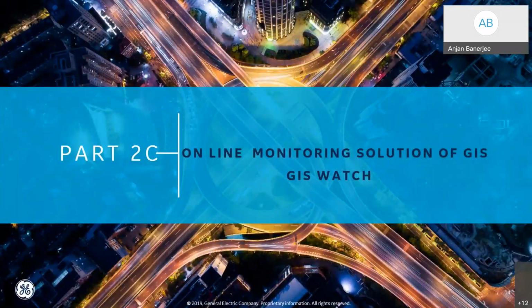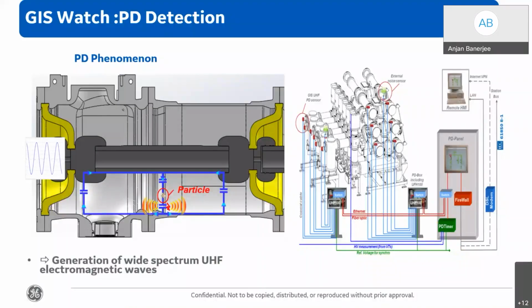Now we will have a look at the online monitoring solution for GIS, which is known as GIS Watch. We discussed a few slides back that the challenging scenario in case of GIS is partial discharge activity. So let us see how a partial discharge activity can be detected by an intelligent electronic device. When we have a partial discharge, which is basically because of, say, a moving particle, as we can see over here, this moving particle would create a partial discharge current path, and then we'll have an ultra high frequency electromagnetic wave generated. These ultra high frequency electromagnetic waves are captured by various antennas which are located at various strategic locations of the GIS, as we can see over here. Over and above, we also provide external antennas because there could be ultra high frequency signals originated due to a noisy environment in the substation.